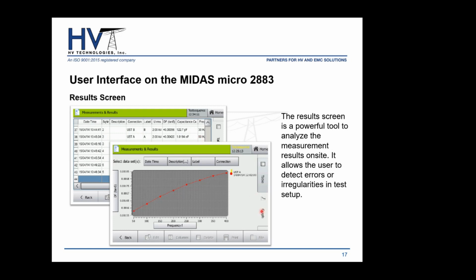Alternatively, if for example you will be doing a frequency sweep and you want a graphical visualization of your results, you can also customize this graph by putting on your y-axis what value you want to see against your x-axis. For example, in this screen, they plotted how dissipation factor is changing depending on variable frequency from 50 to 400 hertz. So you have two choices. You can see it on a table, or you can go ahead and see it as a graph.